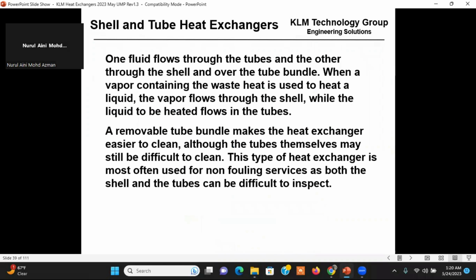One fluid flows through the tubes, and the other fluid flows through the shell and over the tube bundle. The vapor flows through the shell while the liquid flows in the tubes. Removal of the bundle makes the heat exchanger easier to clean, although the tubes themselves may be difficult to clean. This type of heat exchanger is often used for non-fouling services. Both the shell and tubes can be difficult to inspect.